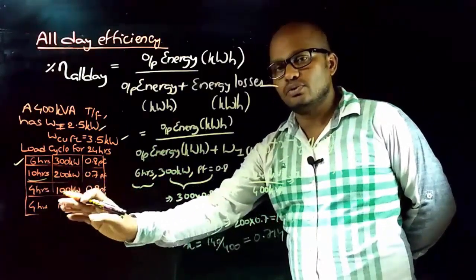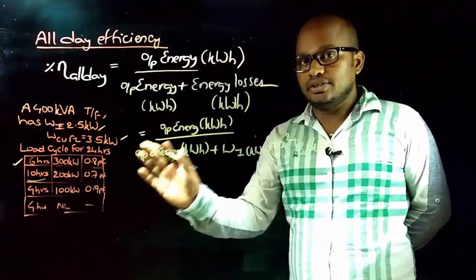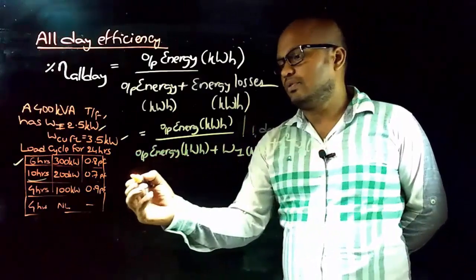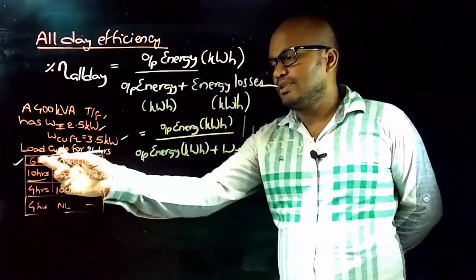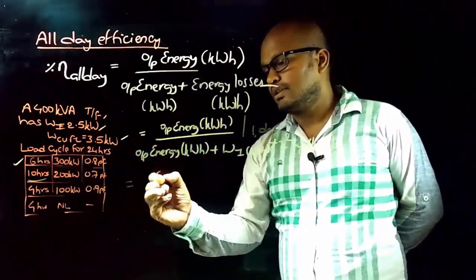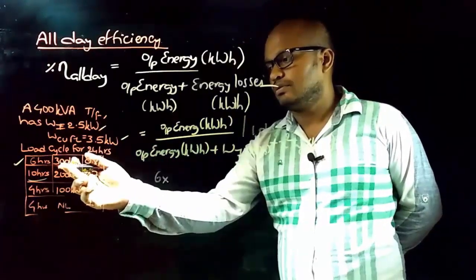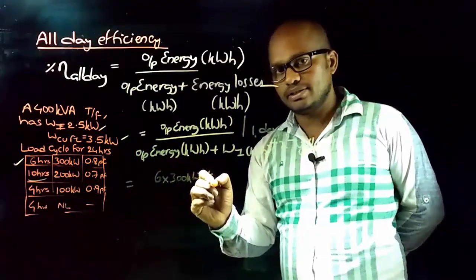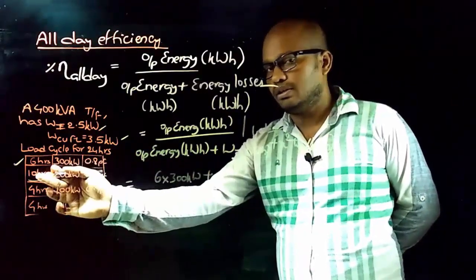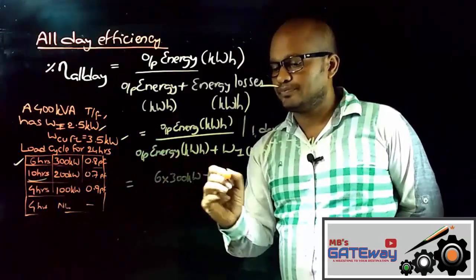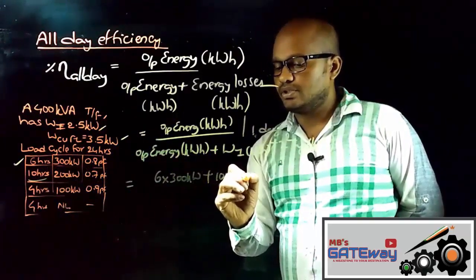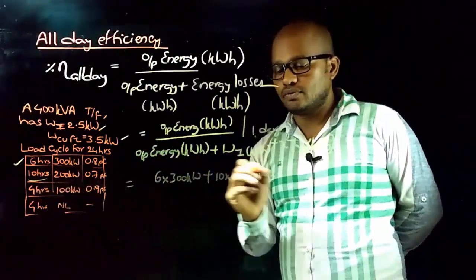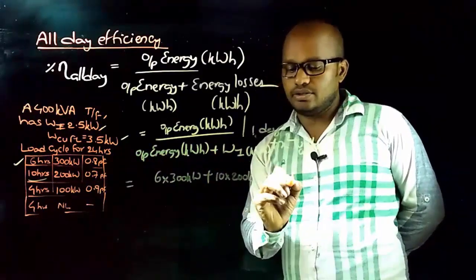For the next four hours there is no loading, so there is no need to find x. We are finding all-day efficiency for one full day. Output energy for the first 6 hours is 6 × 300 kW, plus output energy for the next 10 hours is 10 × 200 kW, plus output energy for the next 4 hours is 4 × 100 kW.